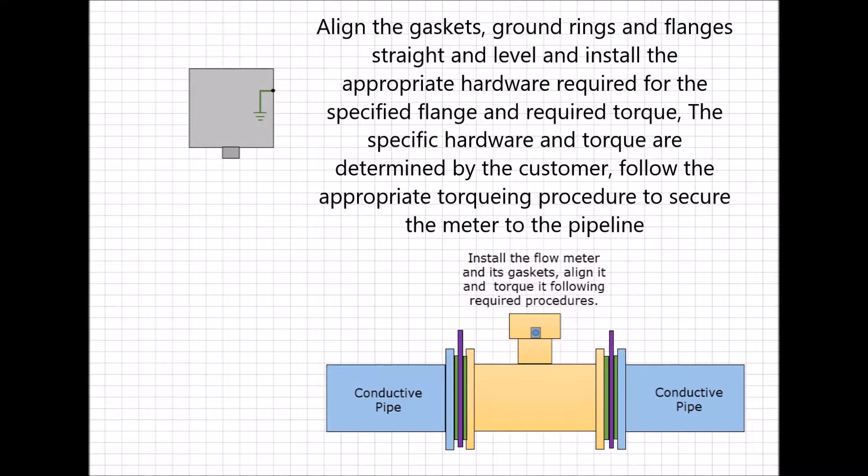Align the gaskets, ground rings and flanges straight and level and install the appropriate hardware required for the specified flange and required torque. The specific hardware and torque are determined by the customer. Follow the appropriate torquing procedure to secure the meter to the pipeline.